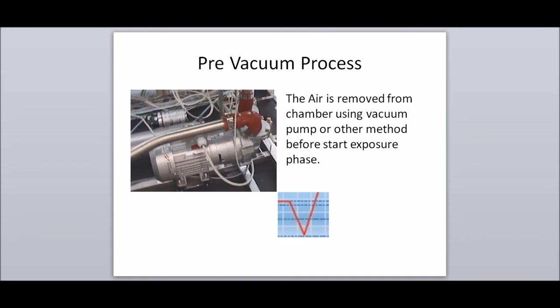Pre-vacuum process: air is removed from the chamber using a vacuum pump or other method before the start of the exposure phase. This method is particularly suited to load items that can trap air, like tubing, pipes, machine parts, and filters.